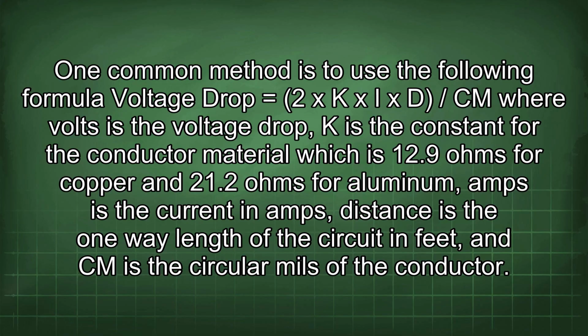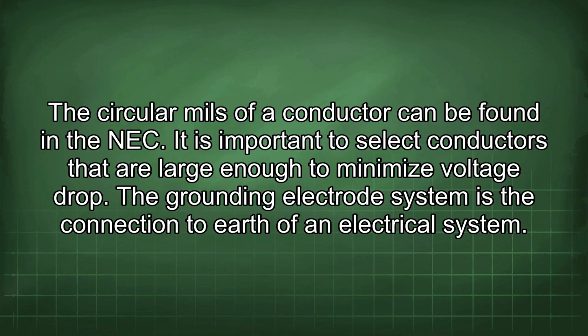2 x K x I x D / CM, where V is the voltage drop, K is the constant for the conductor material, which is 12.9 ohms for copper and 21.2 ohms for aluminum, I is the current in amps, D is the one-way length of the circuit in feet, and CM is the circular mils of the conductor. The circular mils of a conductor can be found in the NEC. It is important to select conductors that are large enough to minimize voltage drop.